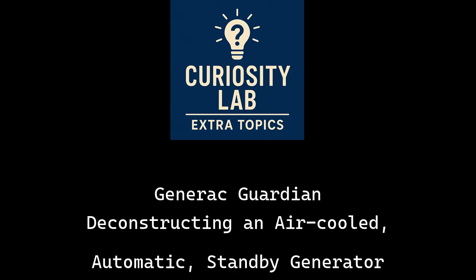That's a perfect analogy. Think about the demand: when a 16 kilowatt generator suddenly gets hit with a huge load, like a 5-ton air conditioner kicking on, it needs a massive instantaneous gulp of fuel to avoid sagging. And the regulator alone can't react that fast. It can't. There would be a split second of fuel starvation, maybe causing a brownout or a stall.